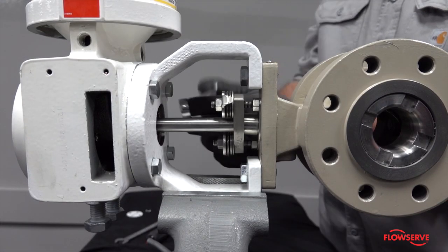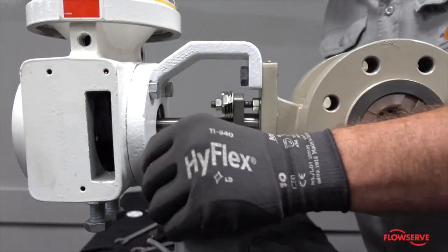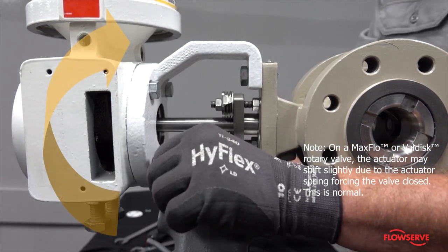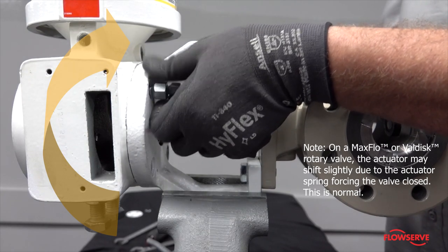Remove the four tapered bolts that attach the yoke to the transfer case. Note: on a MaxFlo or Valdisk rotary valve, the actuator may shift slightly due to the actuator spring forcing the valve closed. This is normal.